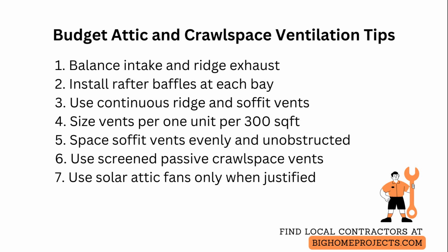Use low-cost solar-powered attic fans only when you can demonstrate a measurable benefit such as extreme attic overheating or inadequate passive exhaust, and ensure they include a thermostat and overrun timer and are wired to disconnect when they create negative pressure drawing conditioned air from the house.